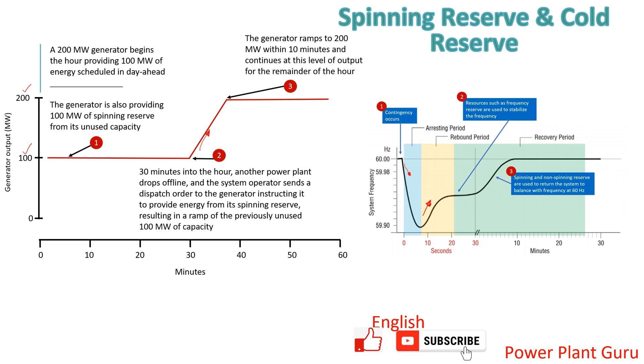These kinds of systems are generally available in gas-based power plants or combined cycle power plants where you have a GTCC or gas turbine which has a very high ramp rate. High ramp rate means a GTCC can go to 50 megawatt per minute also, which is not true in the case of coal-based power plants. These kinds of mechanisms are there to maintain the stability of the power plant power system.